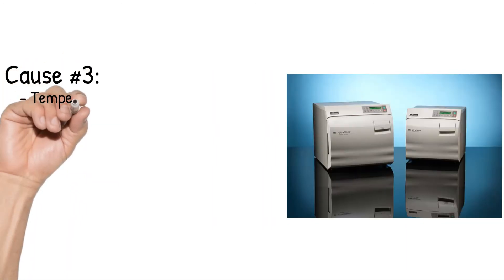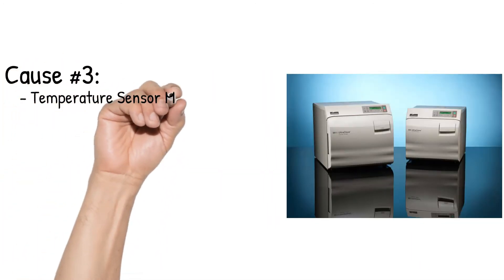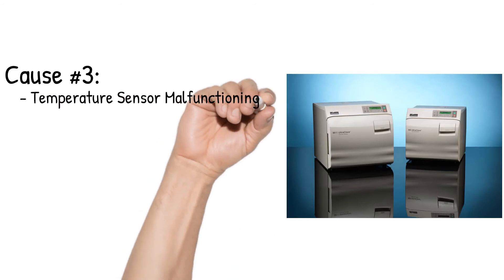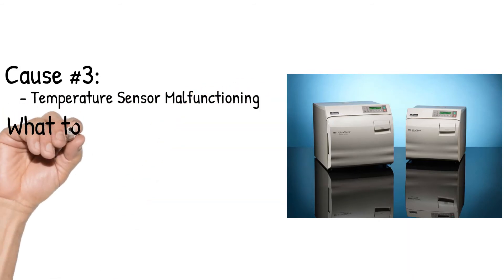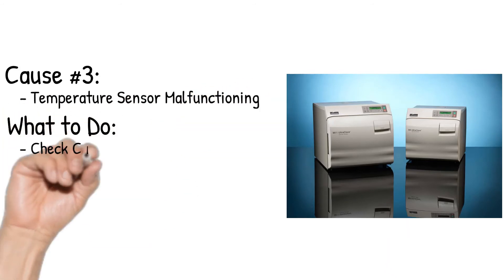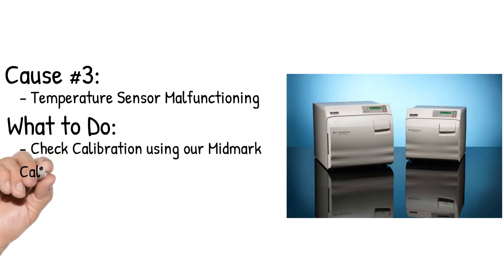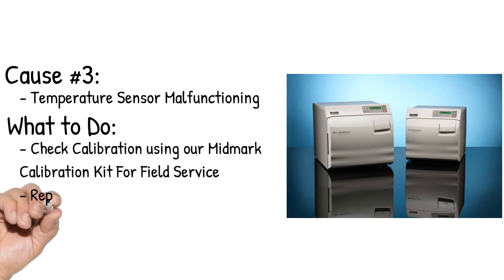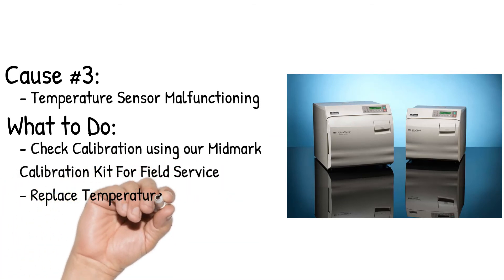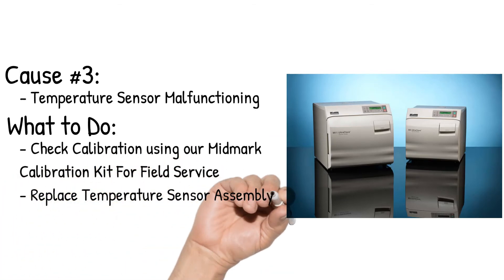Cause number 3: Temperature sensor malfunctioning. What to do? Check calibration using the Midmark calibration kit for field service. Replace the temperature sensor assembly.